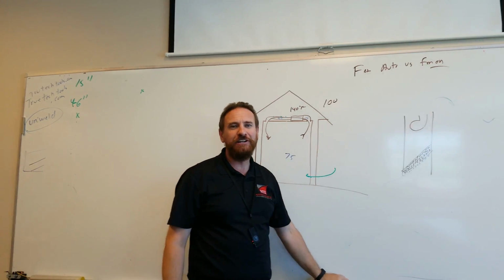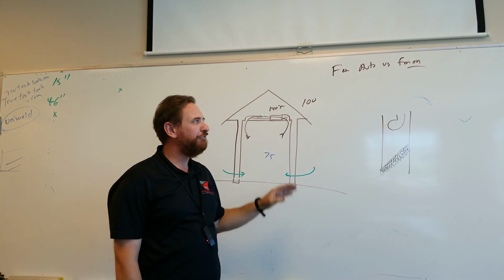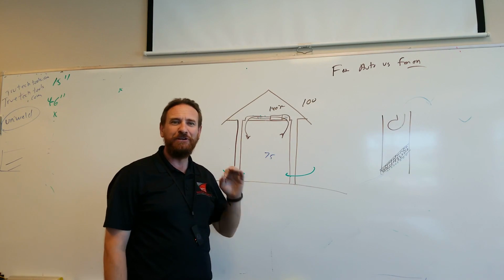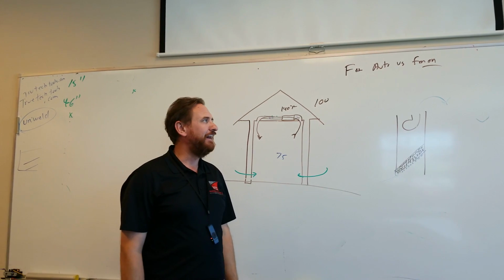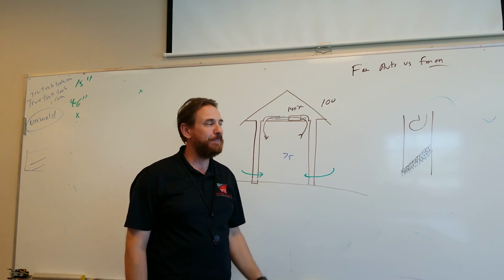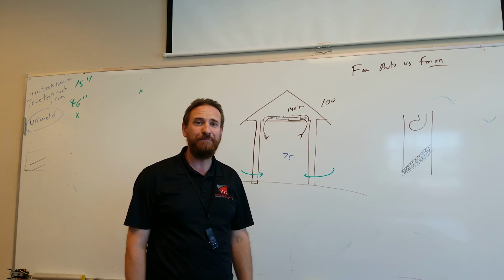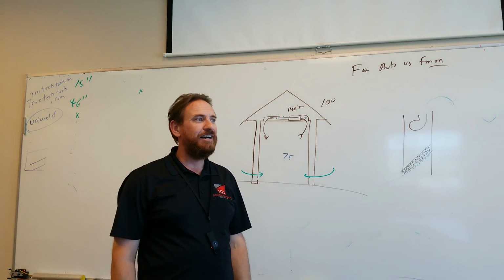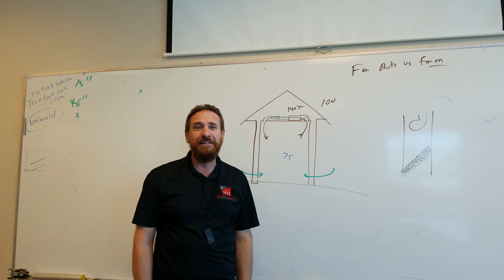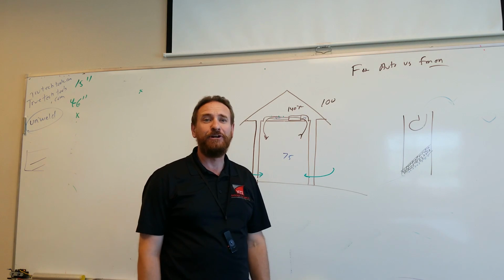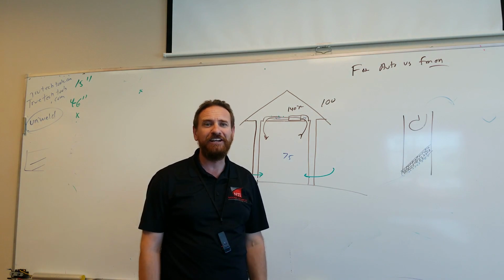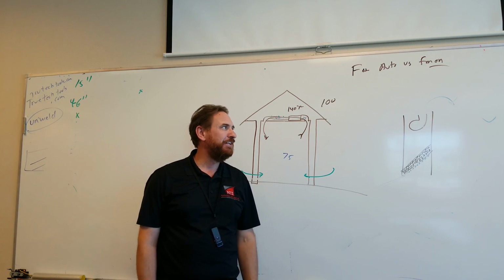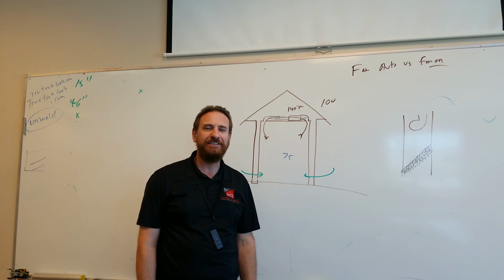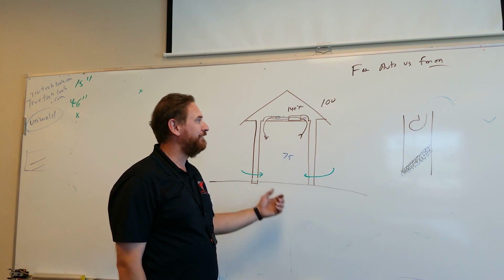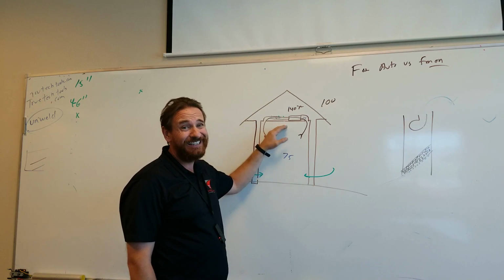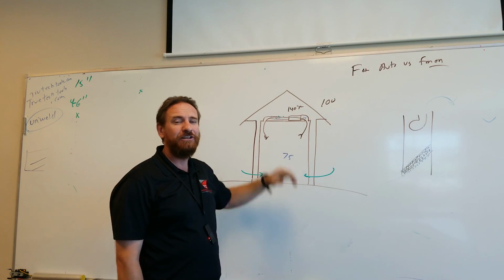Simply on residential, it's probably better to have the fan on auto. For most typical systems you see, there's always exceptions to that rule, and it depends on what part of the country you live at. If you're in the Midwest, where you have ductwork in the basement, summertime, low humidity, then by all means, leave that fan in on position. It's going to help make it more comfortable, especially with an ECM or an X13 motor. But if you live in a humid climate, for sure you want it on automatic. And if you live in a climate like this, where your ducts are in the attic, which isn't the ideal place, you also want it for automatic.